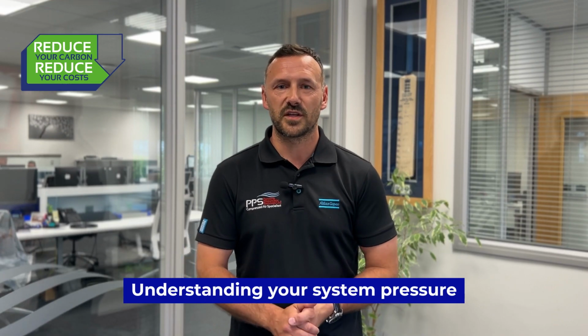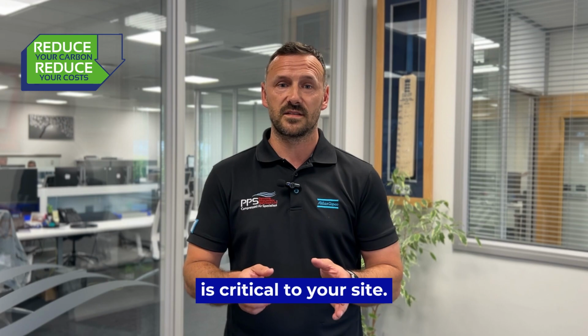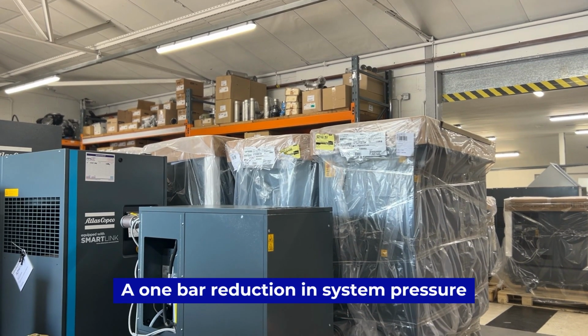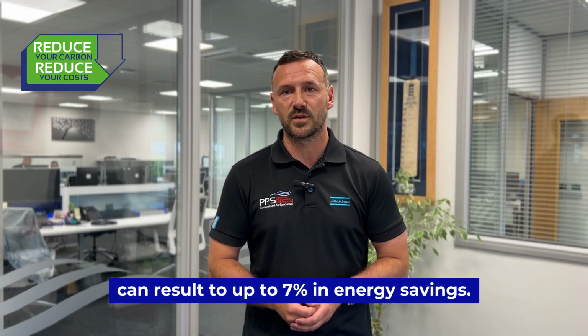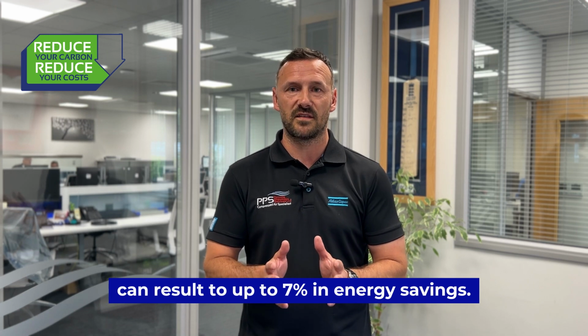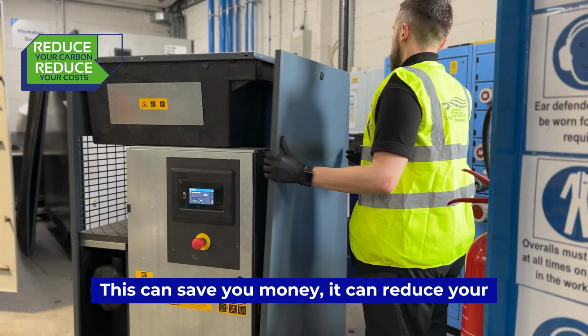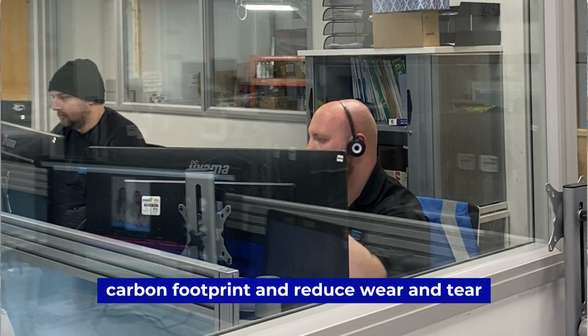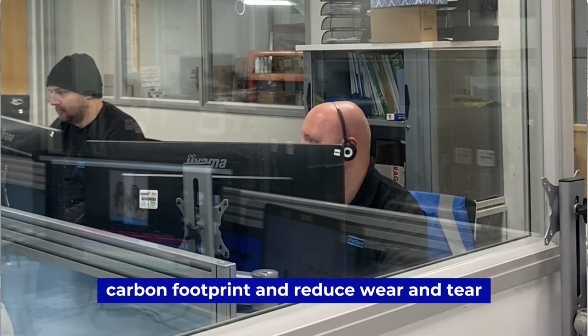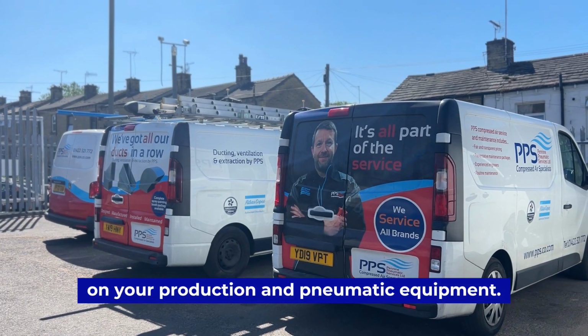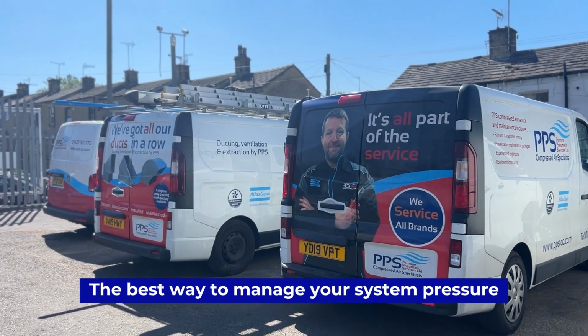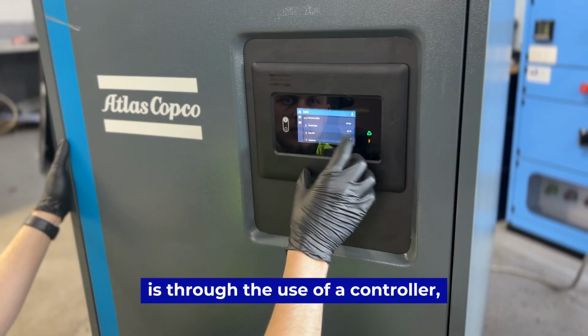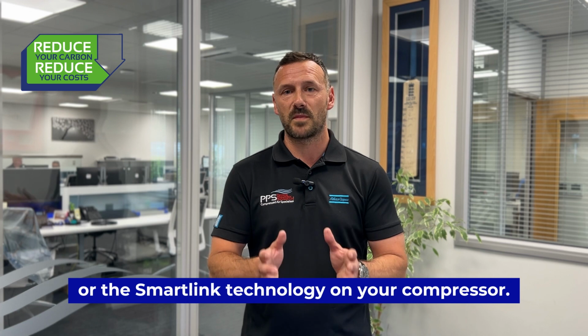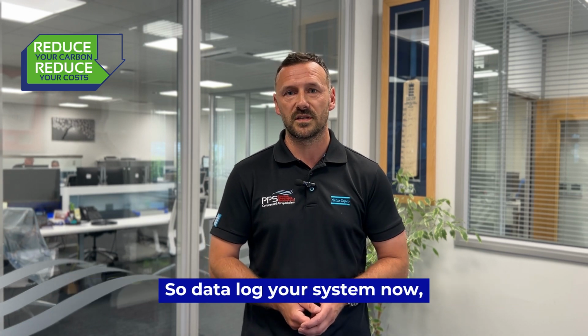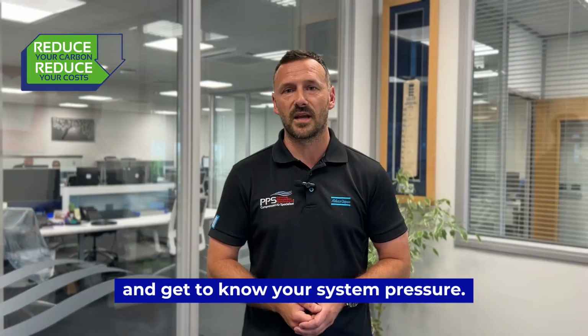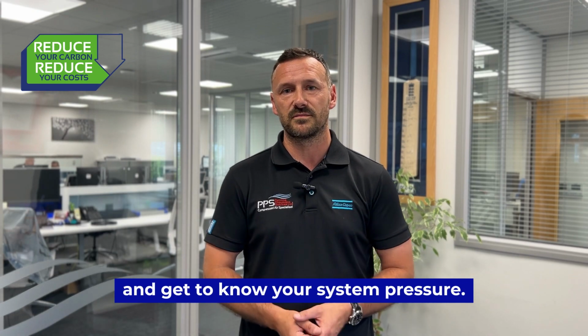Understanding your system pressure is critical to your site. A 1 bar reduction in system pressure can result in up to 7% in energy savings. This can save you money, reduce your carbon footprint and reduce wear and tear on your production and pneumatic equipment. The best way to manage your system pressure is through the use of a controller or the SmartLink technology on your compressor. So data log your system now and get to know your system pressure.